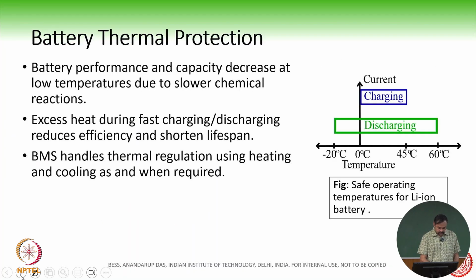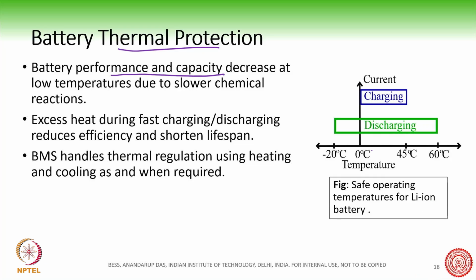Of course, you also have battery thermal protections, which are very important, because battery performance and capacity decrease outside safe ranges. During charging, there's a safe operating area, like between 0 to 45 degrees. During discharge, you can go from -20 to 60 degrees, this whole range.